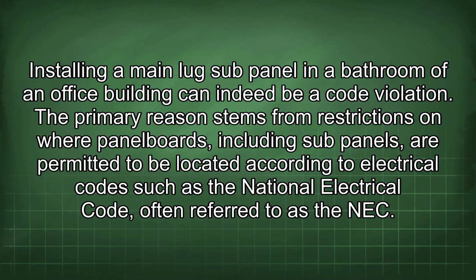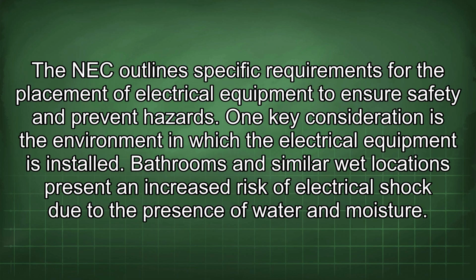Installing a main lug sub-panel in a bathroom of an office building can indeed be a code violation. The primary reason stems from restrictions on where panel boards, including sub-panels, are permitted to be located according to electrical codes such as the National Electrical Code, often referred to as the NEC. The NEC outlines specific requirements for the placement of electrical equipment to ensure safety and prevent hazards.